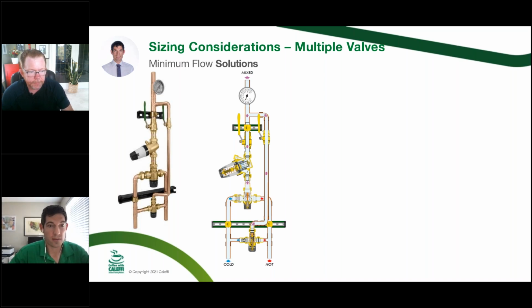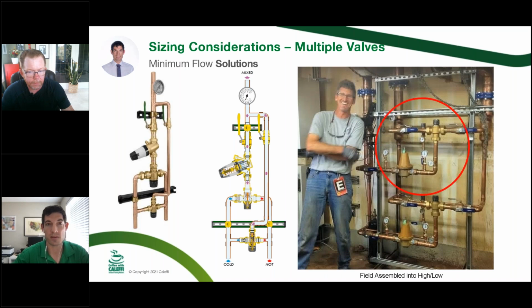So in the past and currently with thermostatic, if you don't have an electronic option, you don't want to go to an electronic mixing valve, you don't need any of the other features there. What you can do is, this is a station that you can buy from Caleffi, a single part number that has a small mixing valve on the bottom. And then as soon as that can't keep up, you start to see some fall off pressure with the PRV in the center there. And then the big mixing valve starts to open. So it's two different valves.